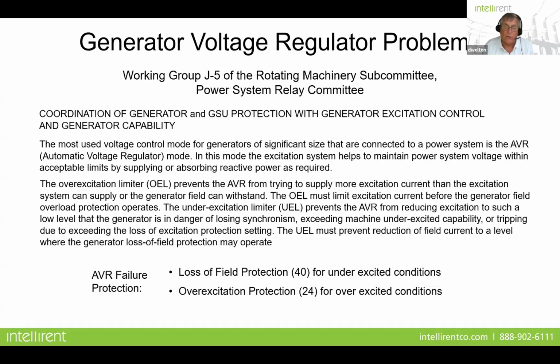And with large generating stations, basically you have your generator, you have the transformer connected to the generator, and then you have your main breaker. Okay, so basically a volts per hertz condition is a reaction to your AVR, or your automatic voltage regulator, having some kind of an issue, where the overexcitation is growing because the frequency and the voltage aren't coming up to speed concurrently. Okay, one's running away from the other. So this could be a problem.